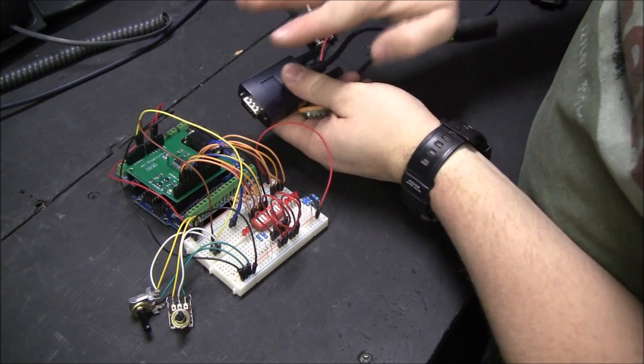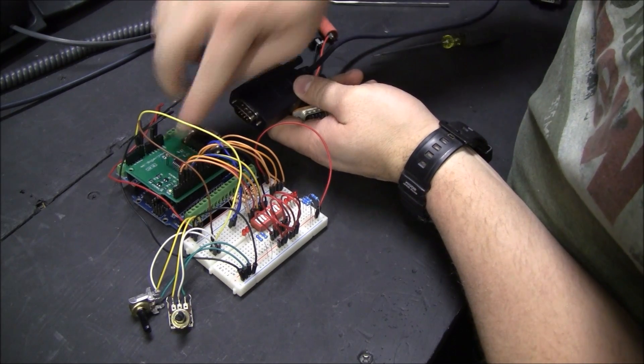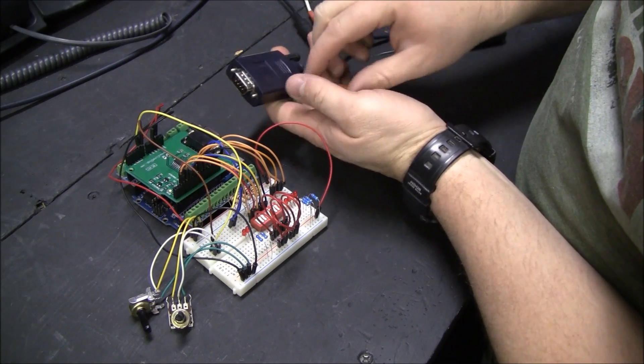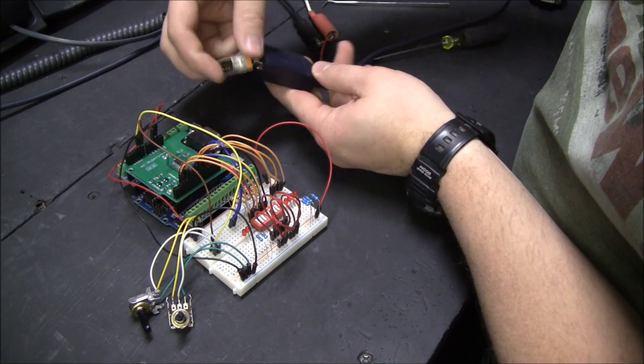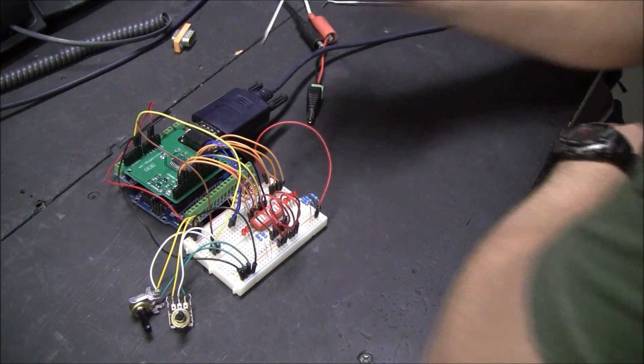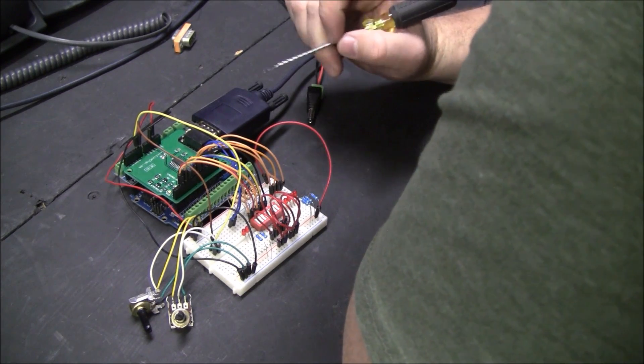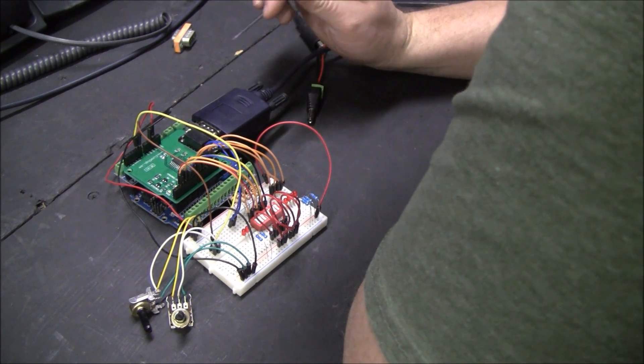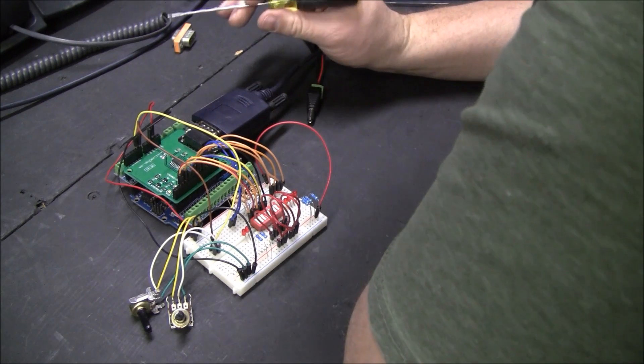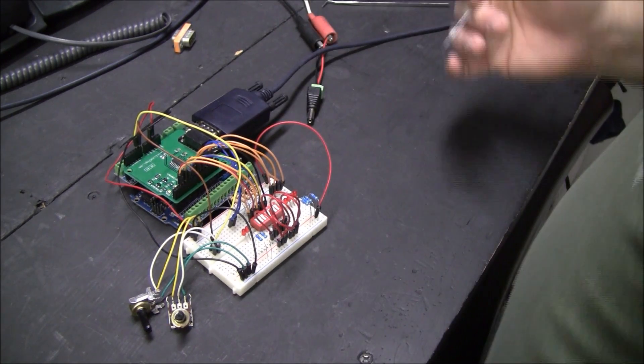You plug it in. Since you have transmit and receive, transmit from here has to go to receive here. So sometimes you need to cross it over with like a null modem adapter. So you could just stick that in there and it'll cross the pins over. This actually works. RS485 is a lot more finicky and you can spend a lot of time trying to get the drops to work out. And you might need to have pull down or pull up resistors on the end of your run.